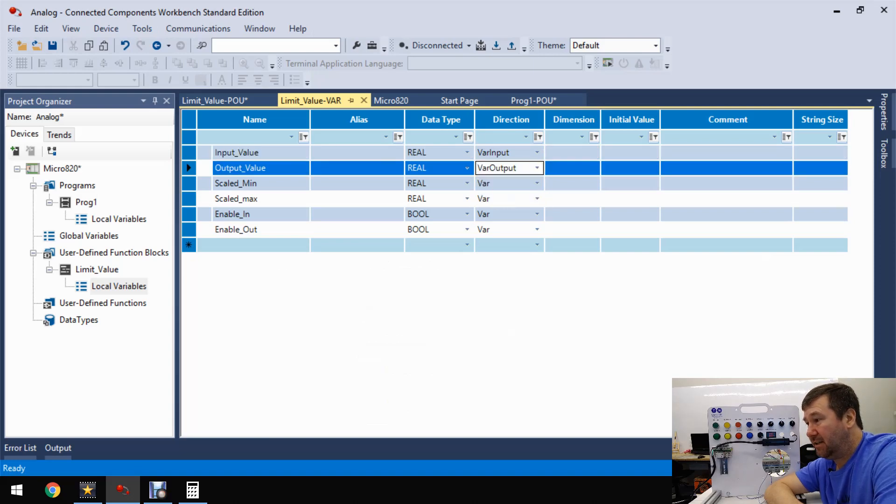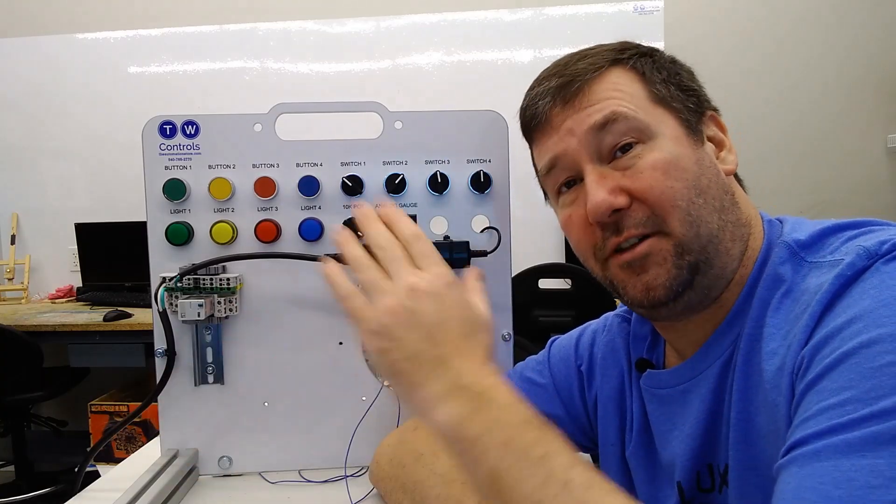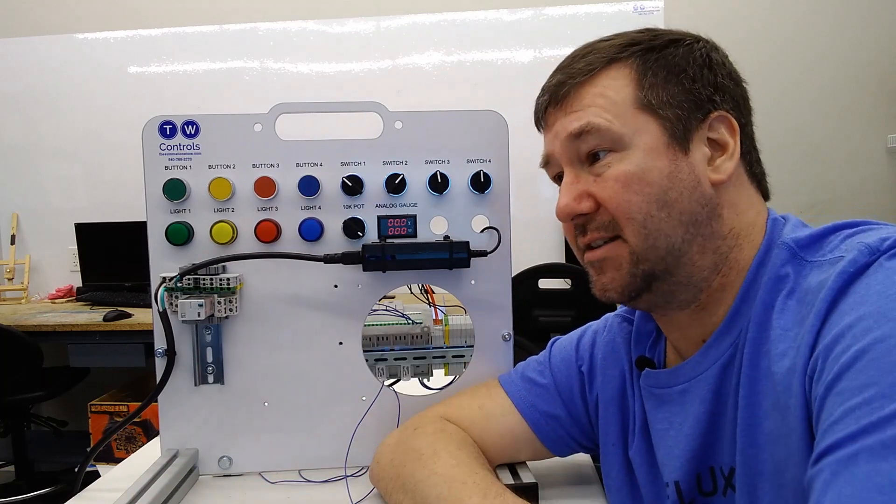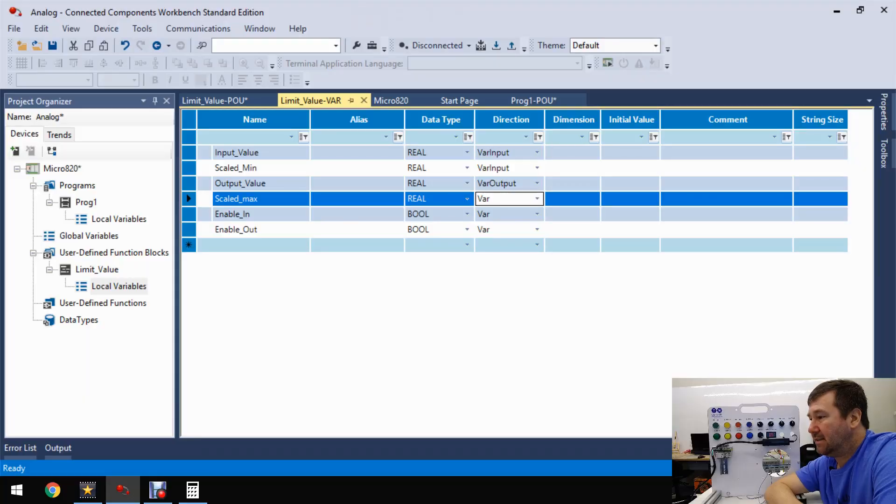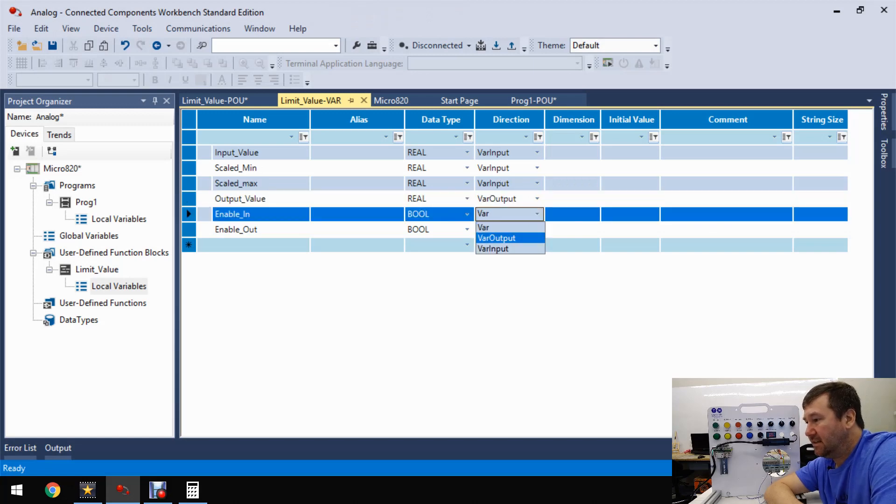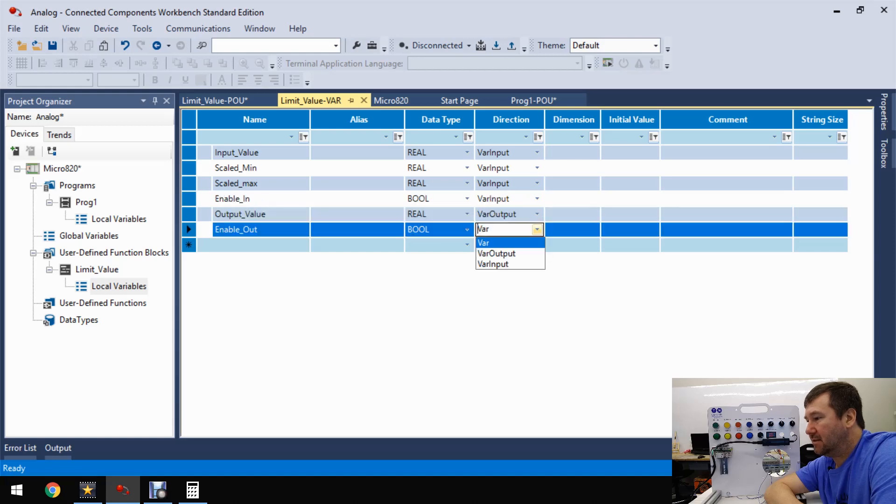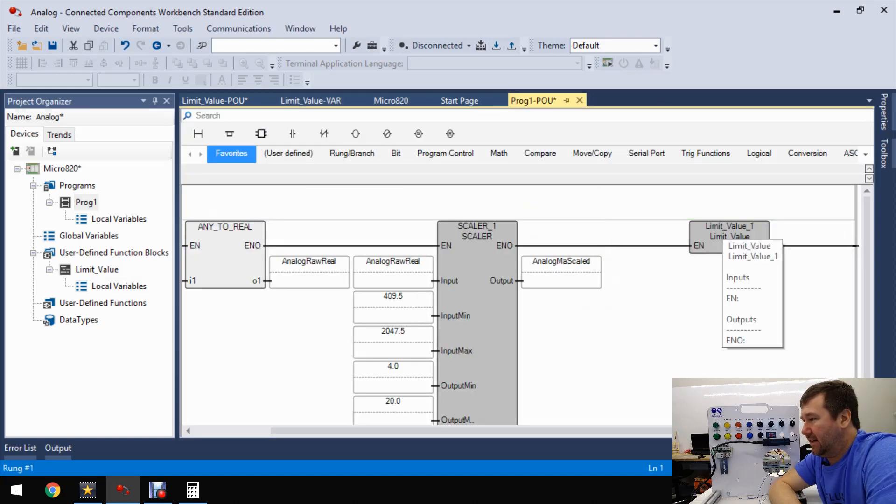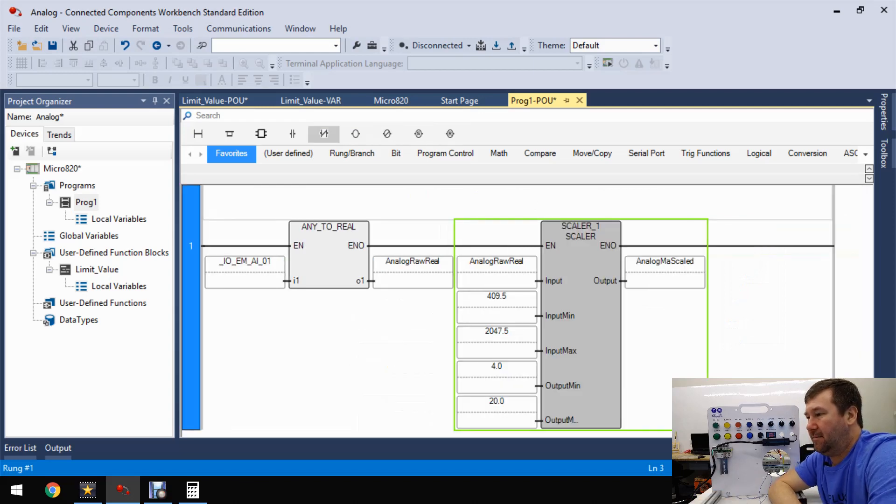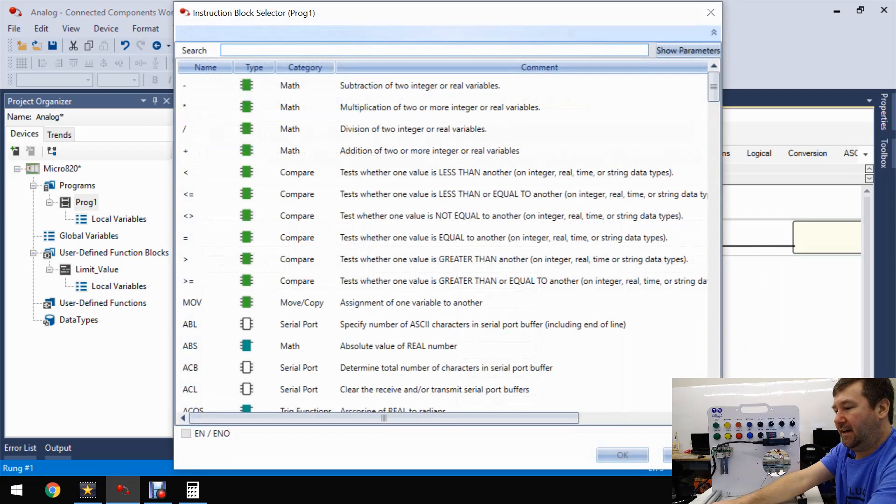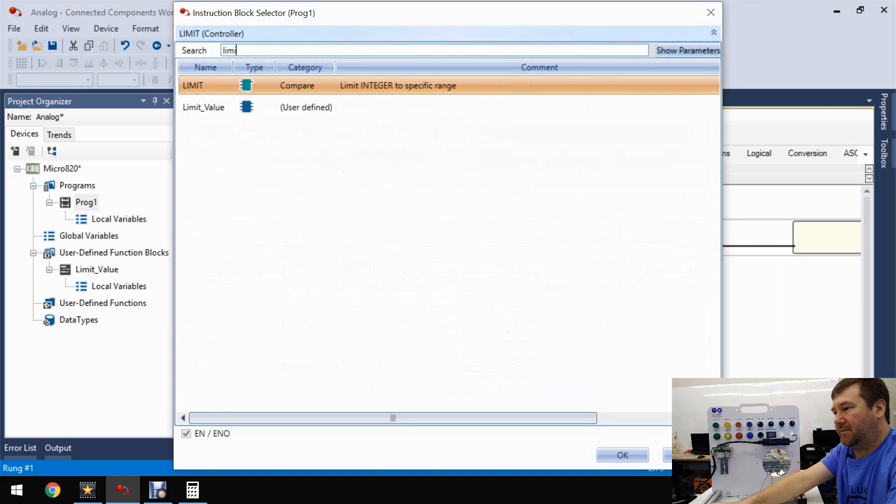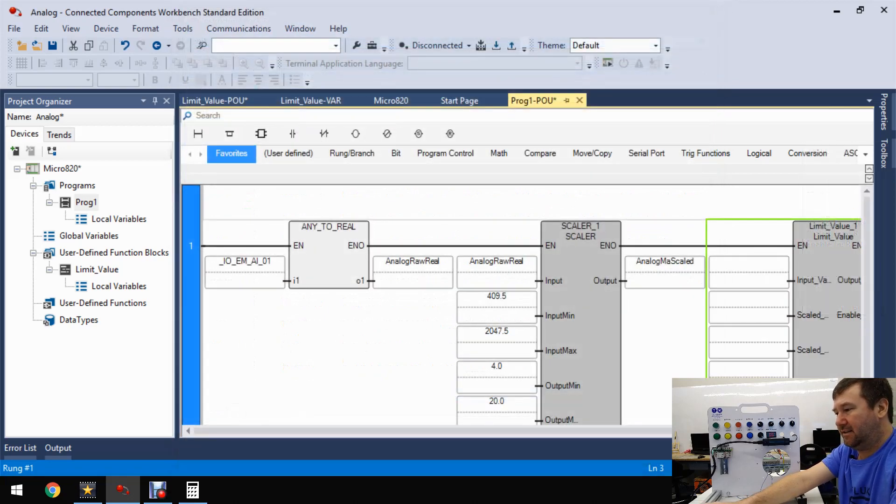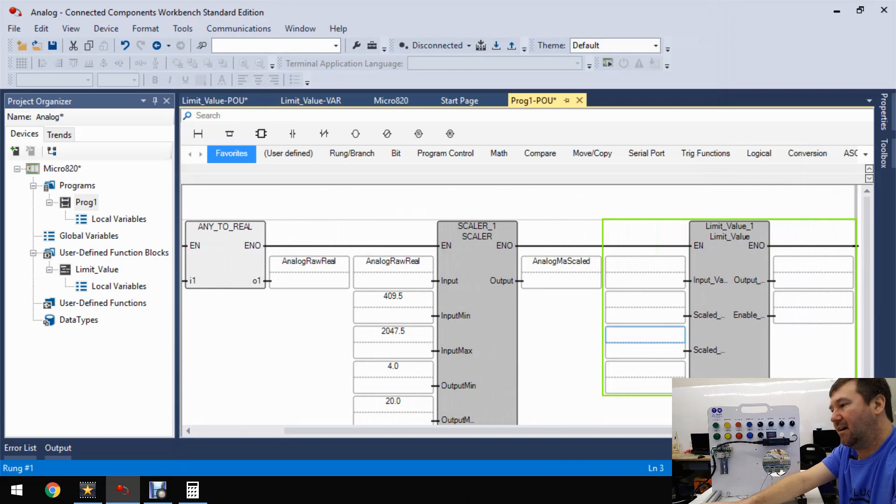So this analog milliamp scaled is the one that was looking like it was going to be off. So let's go ahead and add an instruction block. And now we can type limit value, and there you go - there's our user-defined instruction block that we made. And none of our variables are there because I forgot to declare these as input and output variables in their local variables. So let's go back down here to limit value and local variables. So we have like this scaled input value, and right now direction is just an internal variable. We want it to be an input variable. The output value, that's an output variable.